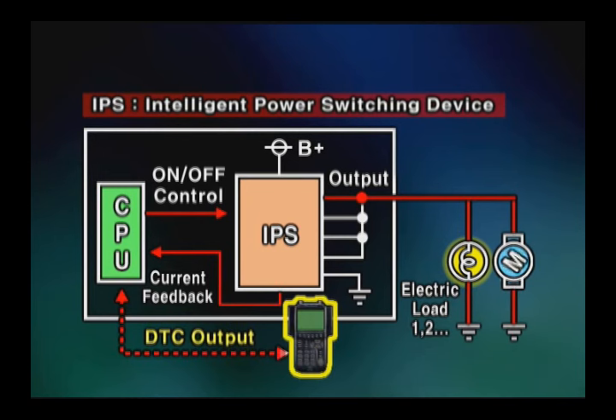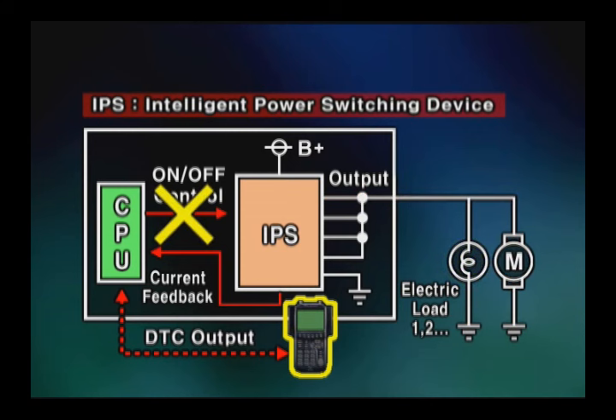If it decides there is a short, the CPU cuts off the operation command sent to the IPS to cut down the electric power. These electric devices do not have a relay or fuse.